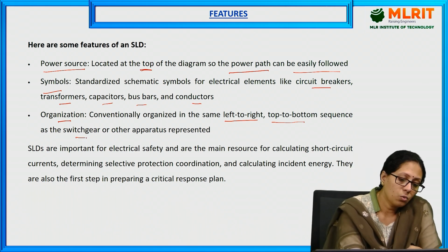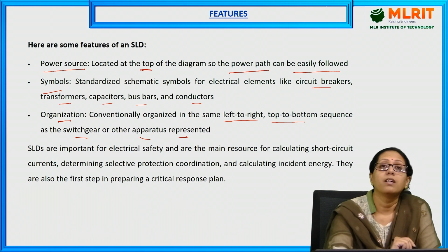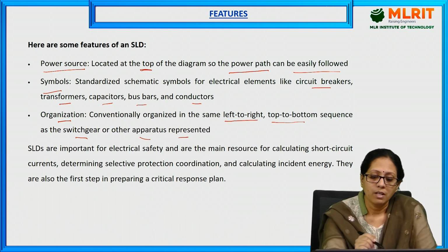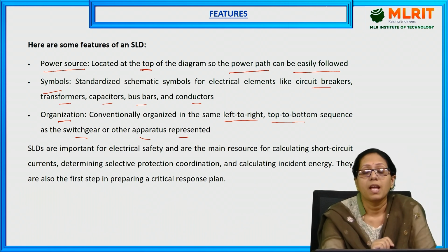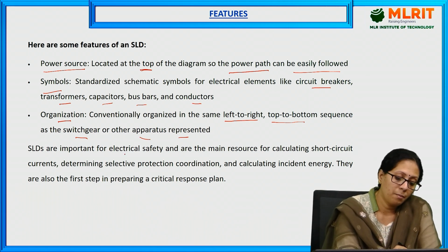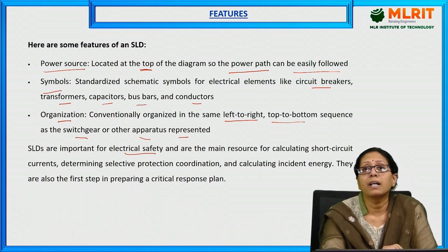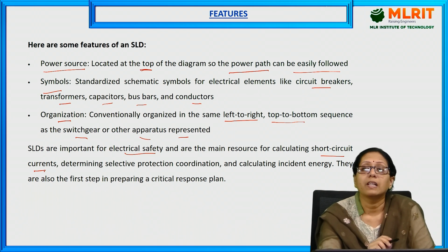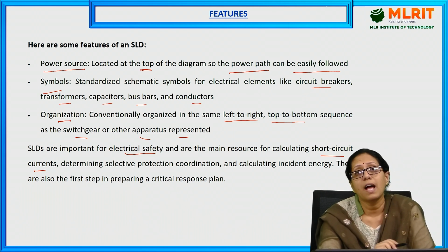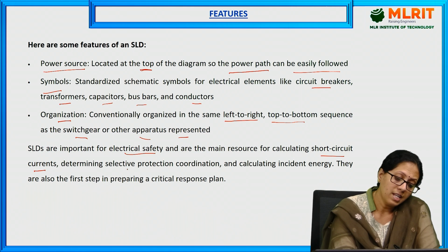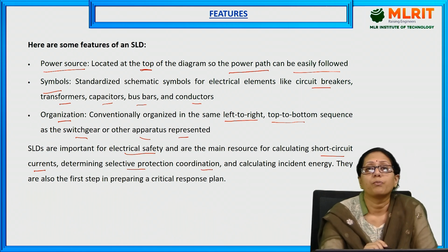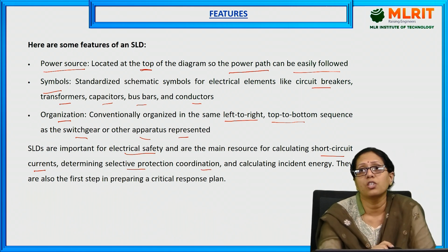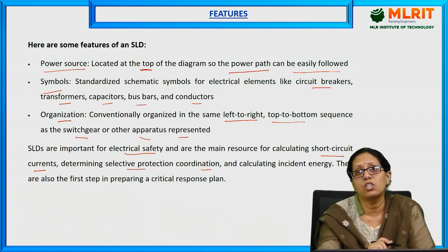As the switchgear and other apparatus are required for controlling in this SLD system. SLD systems are important for electrical safety and are the main resource for calculating the short circuit currents, as well as determining the selective protection coordination and calculating the energy.